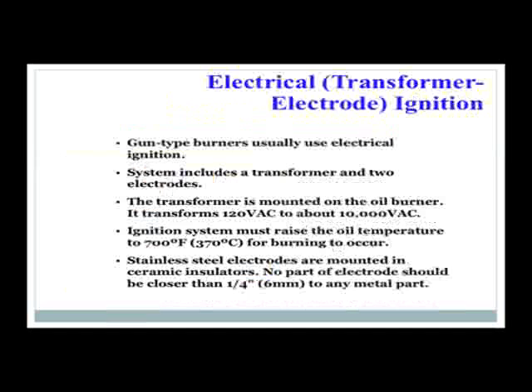Gun-type burners usually use electrical ignition. Systems include a transformer and 2 electrodes. The transformer is mounted on the oil burner, and it transforms 120 volts AC to about 10,000 volts. The newer systems are running closer to 20,000 volts. The ignition system must raise the oil temperature to 700 degrees Fahrenheit for burning to occur. The stainless steel electrodes are mounted in ceramic insulators.